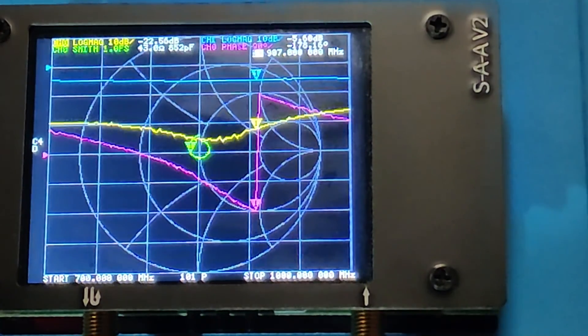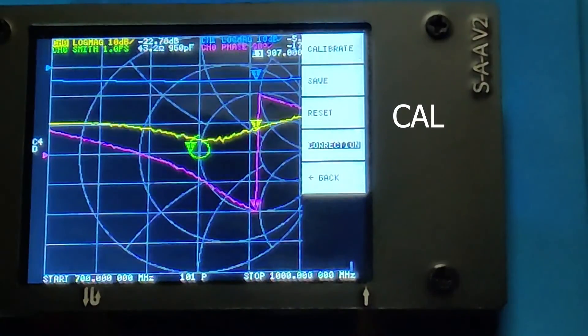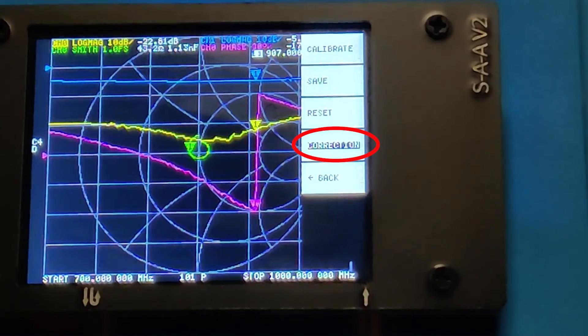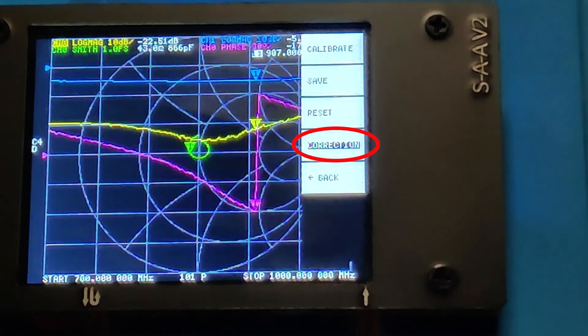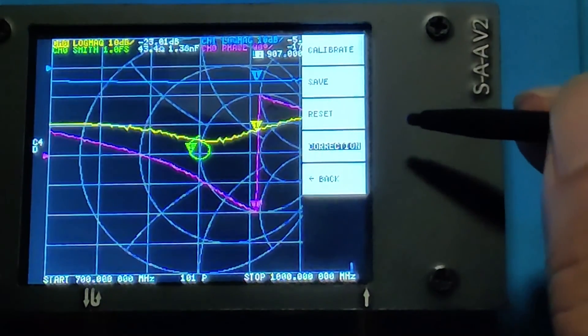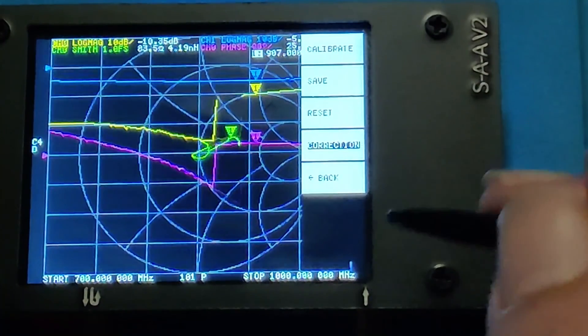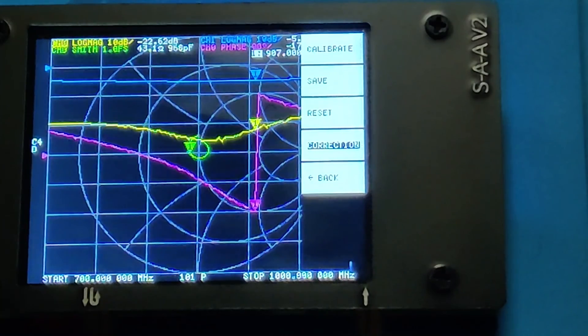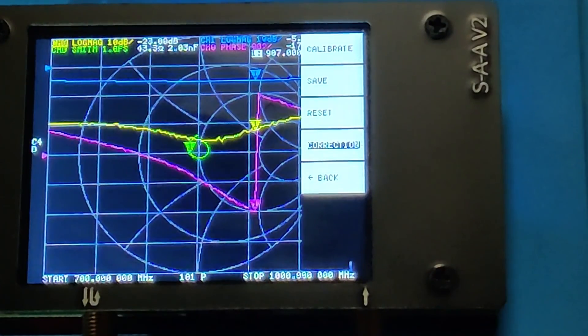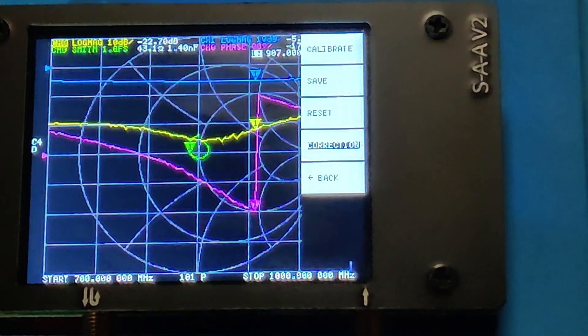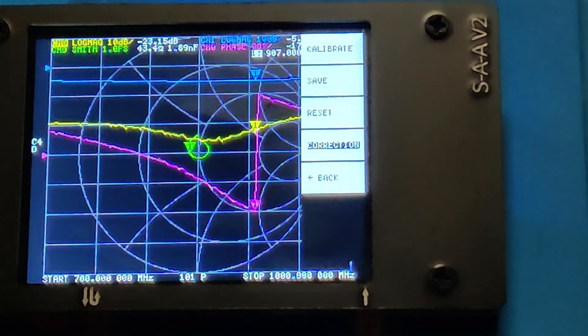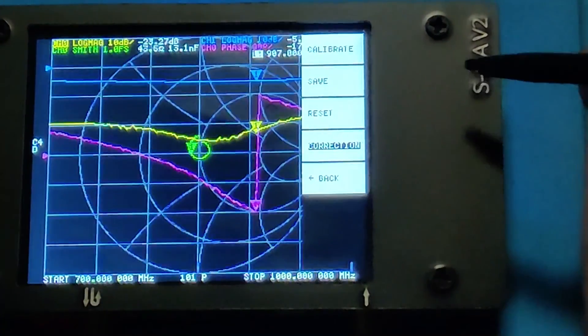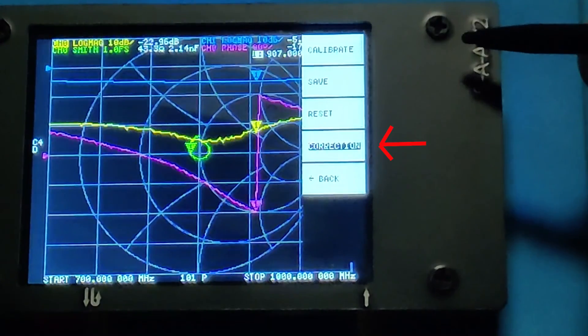Now click on calibration and as you can see, correction is highlighted. This means it has detected that there is a previous calibration saved in this location. If we are doing S21 calibration fresh and we want to erase anything previously stored in this location, we will click on reset. But for this video do not click on reset.